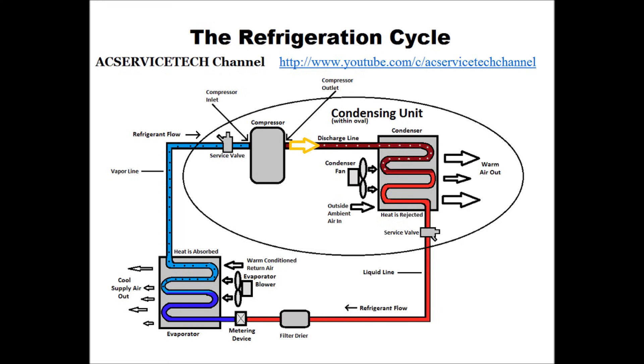As it enters into the condenser coil it starts rejecting heat. As it rejects heat it starts turning into a saturated state in the middle of the condenser coil. A saturated state is where vapor and liquid both exist at the same time. Right after the saturated state where it turns into a complete liquid until it comes out right next to the service valve — that temperature decrease as it's rejecting heat in liquid form is called subcooling.